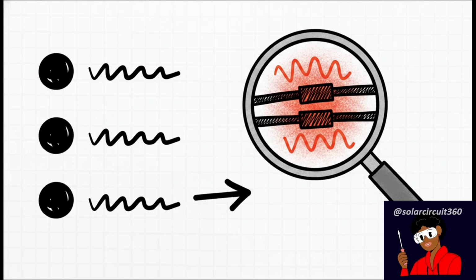You verify the solar production, the protective devices, and your terminal integrity. But notice that final step, perform a thermal inspection under load. A connection can easily pass a basic voltage test, but still become a really dangerous fire hazard once high current starts flowing. Heat indicates resistance. Resistance indicates energy loss. And excessive resistance, well, that becomes a fire. When all these measurements, the voltage, the current, the continuity, and the thermal data, match our design expectations, only then is the system truly ready for service.